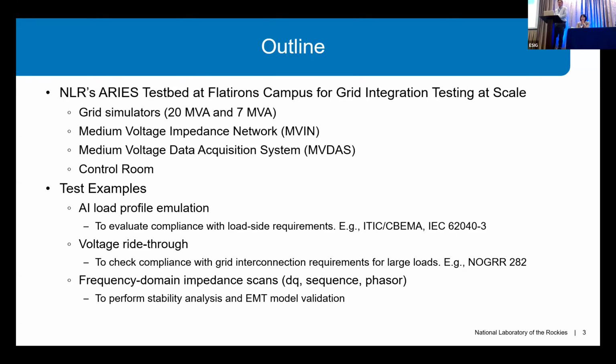I'll start off talking about the hardware setup. Shahil's going to talk about the testing. The hardware setup involves our 2 grid simulators, medium voltage impedance network. We'll talk a little bit about our medium voltage data acquisition system, which is really key for this work. And we'll also go through our control room a little bit too, as that's a new addition to our setup at Flatirons campus. Shahil will talk about our AI load profile emulation and the voltage ride-through testing we've done, and also the frequency domain impedance scans for looking at stability analysis and also model validation.